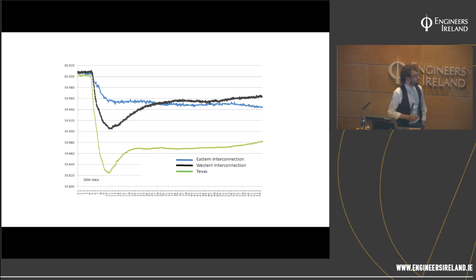So here's the frequency response of the three systems. In blue you have the Eastern interconnection. You can see that the rate at which its frequency falls is less than the Western interconnection, which is less than Texas. That's because the rate at which the frequency falls is inversely proportional to the inertia on the grid. So you can see that the more inertia you have on the grid, the slower the frequency falls, and as a consequence, you're less likely to get in trouble.